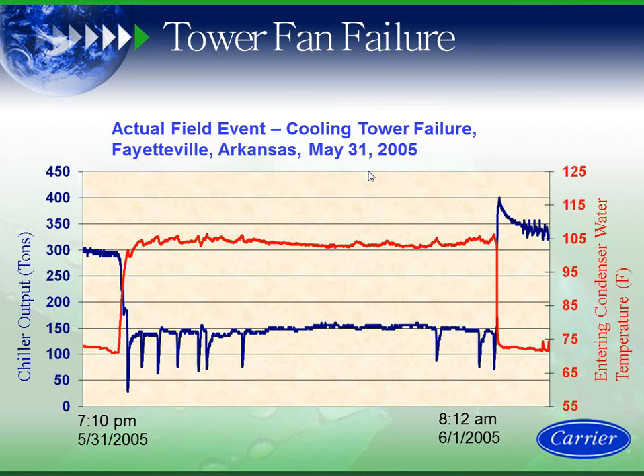So we combed through all the data and came up with the following chart. We show here that the condenser water temperature went from 72 degrees all the way up to 105 degrees, and it ran with 105-degree entering condenser water temperature for 12 hours. It didn't run at 300 tons, but then again, no chiller out in the marketplace would run with 105-degree condenser water temperature. That's not a positive displacement machine. But the Carrier 23XRV did, and it delivered 150 tons for 12 hours while that tower fan was repaired. Once the tower fan was repaired, it went back up. So this building was not without cooling at all. This is very significant when we talk about chillers and overall system reliability.